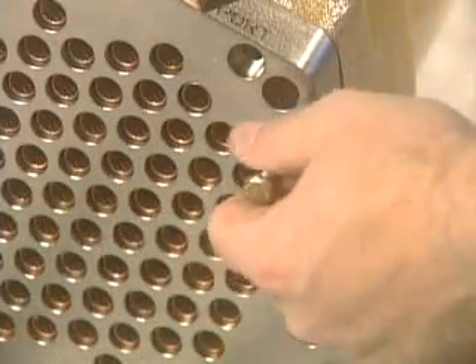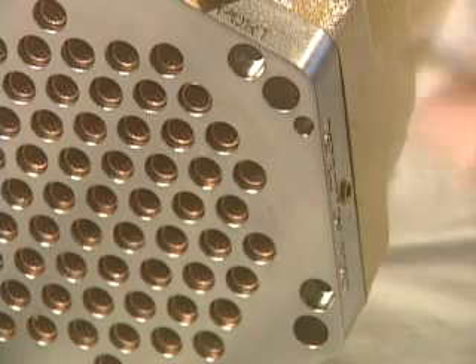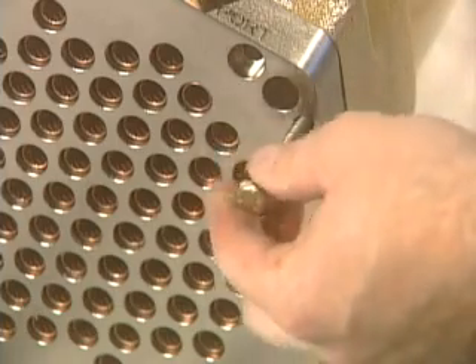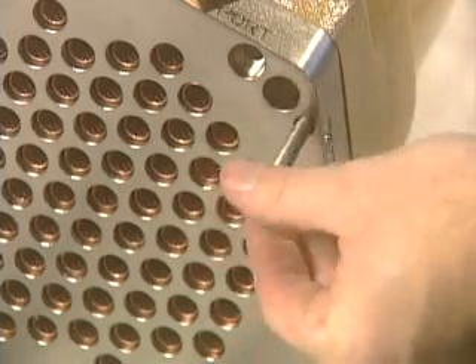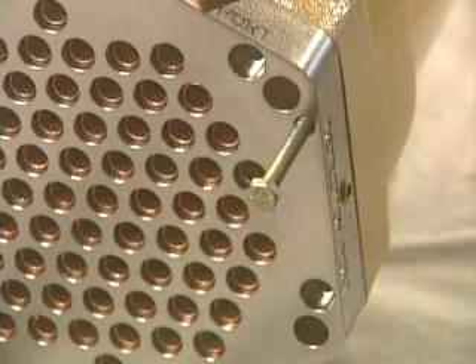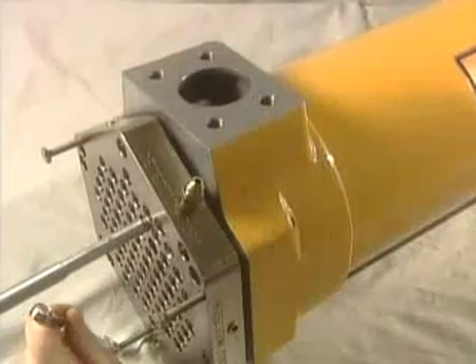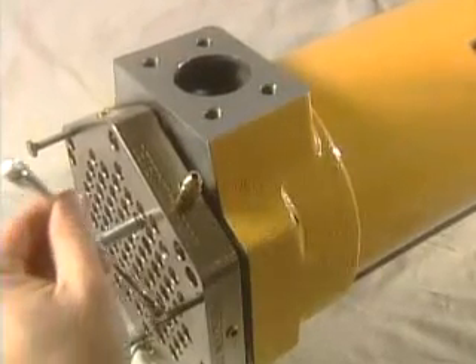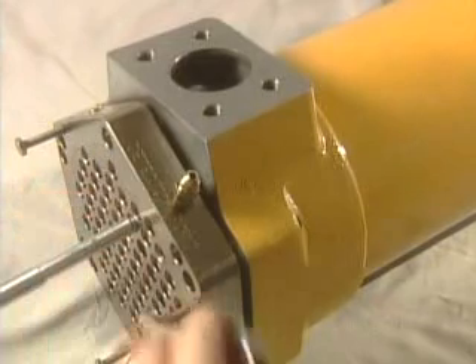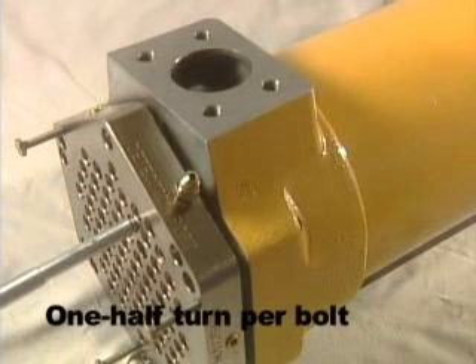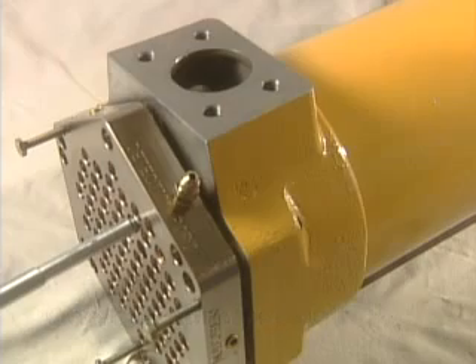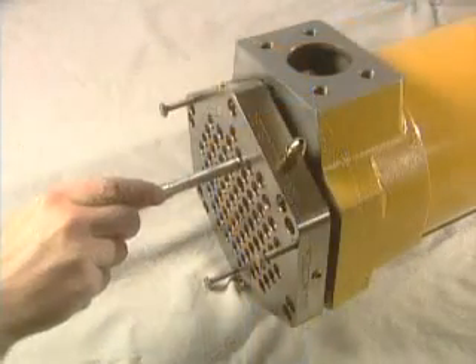Remove header plate retainer bolts. Install bolts with at least 3 inches of thread into the back-out holes and run them in so that they are tight against the shell flange. Once the back-out bolts are in contact with the end flange, remove the header plate from the end flange by turning the back-out bolts no more than 1/2 turn per bolt. The header plate must remain parallel to the end flange, or tube damage may occur.